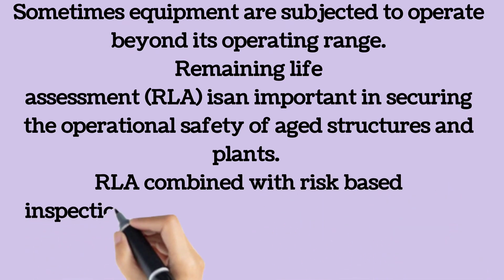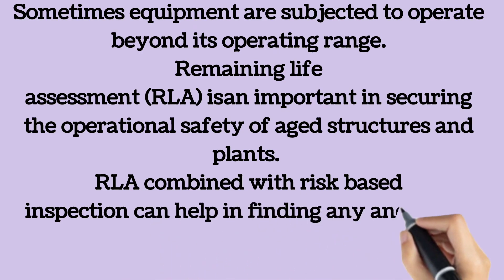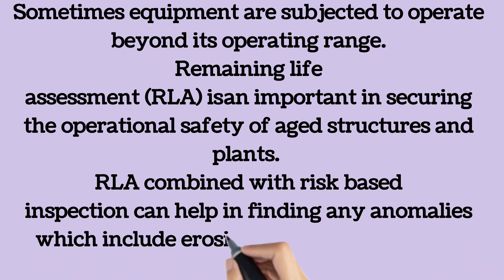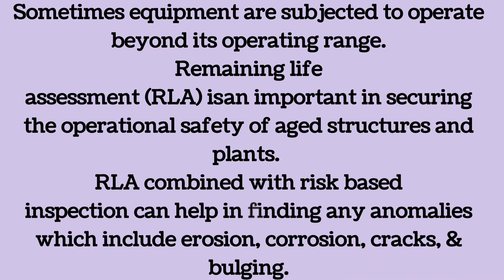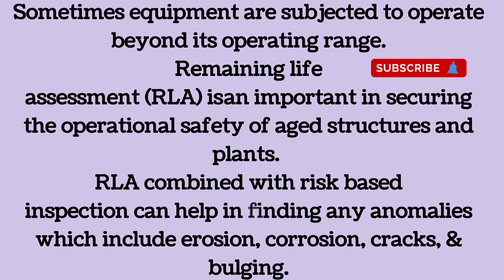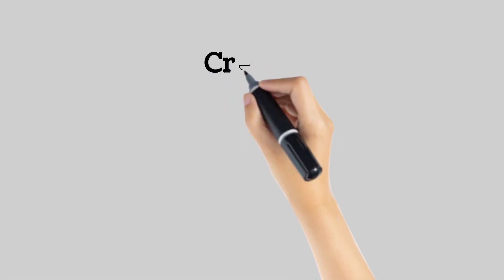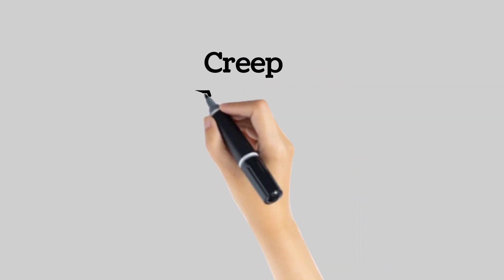RLA combined with risk-based inspection can prevent unforeseen outages and failures that can have tragic and costly consequences. In RLA, multiple non-destructive and metallurgical tests are done for accurate measurement of thickness, dimensions and finding any anomalies which include erosion, corrosion, cracks, bulging, etc. A comprehensive assessment and implementation of its recommendations provide reliable and trouble-free operation and prevent forced outage. Creep is an inelastic, time-dependent deformation that occurs when a material is subjected to stress at a sufficiently high temperature.